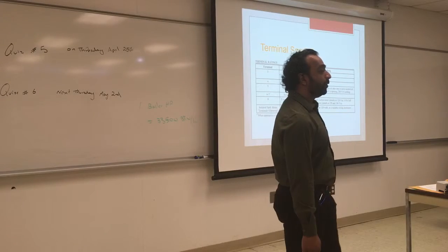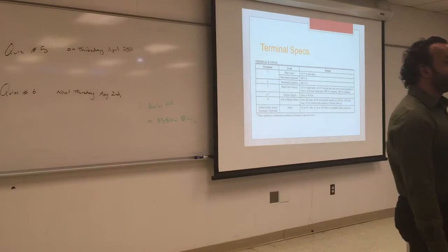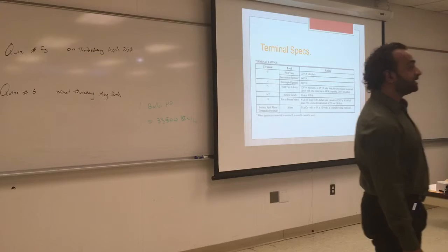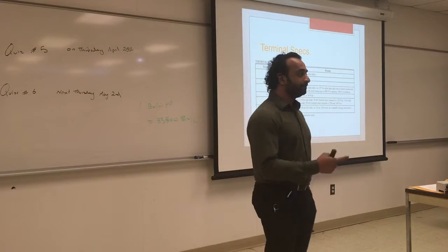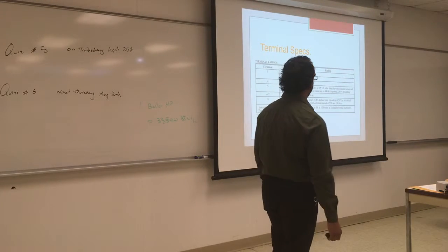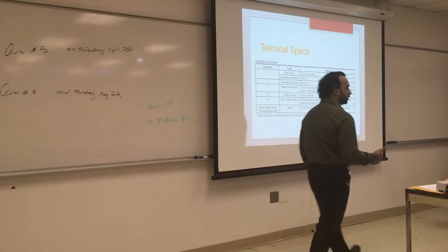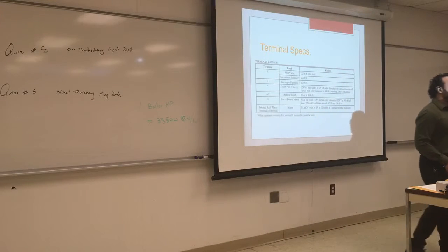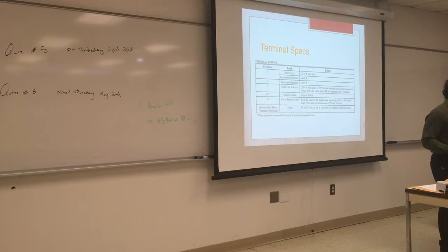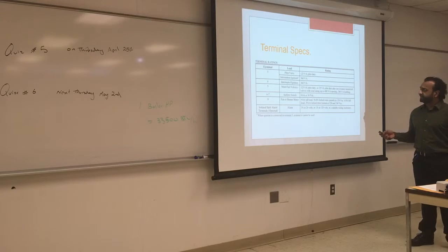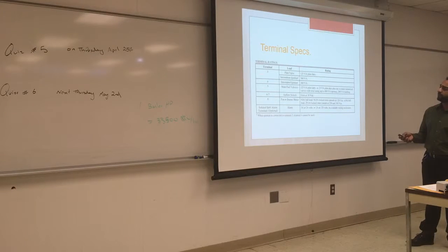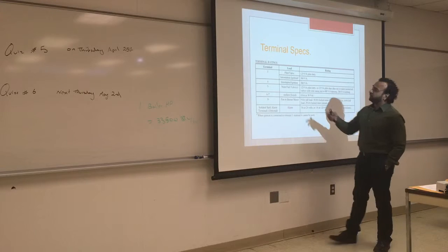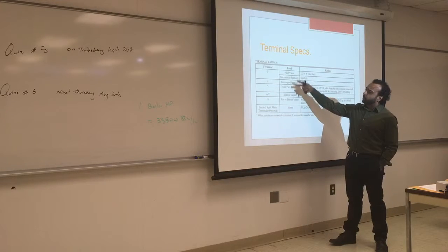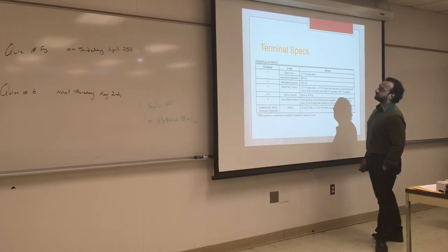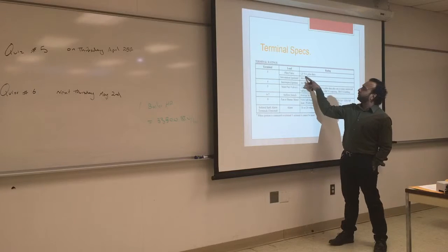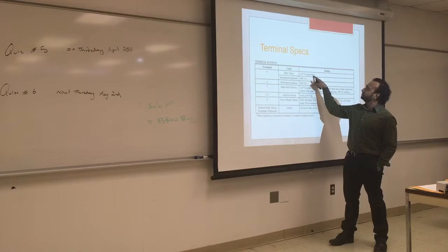Terminal specification. Why do we need to know those specifications? In case you are in charge of troubleshooting those controls, probably you're going to get some extensive training to be able to diagnose these things. But this at least you can pull out from the manual, and they will tell you how much voltage you expect and how much wattage you pull out of each terminal. So for terminal 3, we have 125 VA pilot duty.